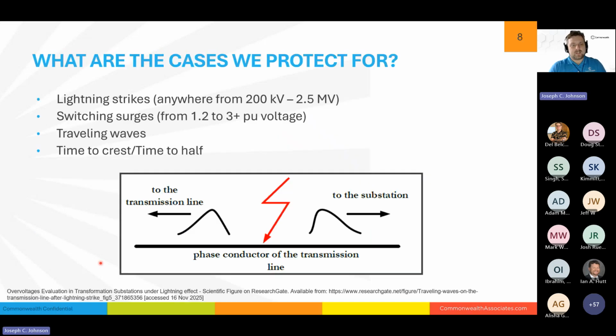So what are these cases that we're protecting for? We're protecting for lightning strikes and switching surges primarily. The lightning strikes can enter a substation anywhere from 200 kV to 2.5 megavolts. When they actually strike a line, you can see surges or voltages at around 15 to 17 megavolts potentially, but by the time they've reached the substation, they've gone through some impedance, they've attenuated down, they've reflected, which we'll all get into things like this later, but they generally are a lower magnitude once they actually enter the substation. A switching surge can be 1.2 to 3 per unit voltage, which is why as you start getting up to those higher voltages, you're getting a multiplier on your voltage, which is why switching becomes much more impactful at the higher voltage levels. Well, what do these look like?